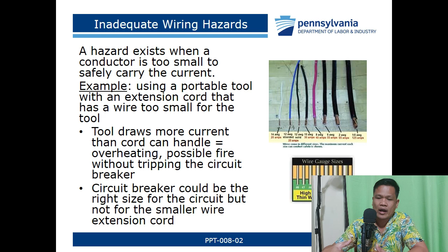We have also inadequate wiring hazards. A hazard exists when a conductor is too small to safely carry the current. Example, using a portable tool with an extension cord that has a wire too small for the tool. So the tool draws more current than the cord can handle, and it can result to overheating or possible fire without tripping the circuit breaker. So minsan, yung electricity or the load is very high, hindi kaya ng mga ginagamit nating mga cord. So it imposes hazard. So circuit breakers could be the right size for the circuit but not for the smaller wire extension cord.